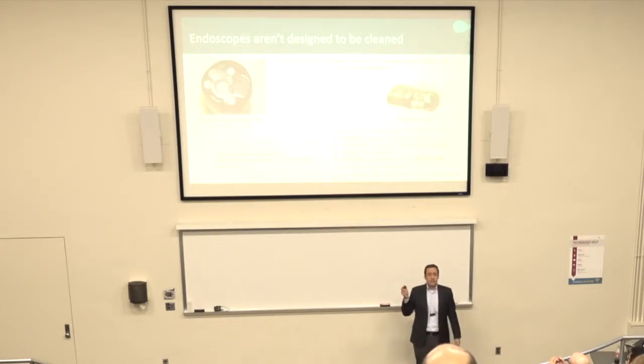Now, on the right, you can see actually the working end of one of those duodenoscopes that have been associated with the outbreak. You can see how hard that would be to clean. On the left, you see biofilm on the end of a colonoscope, and that was actually cleaned. That's the source of infection outbreaks right there.